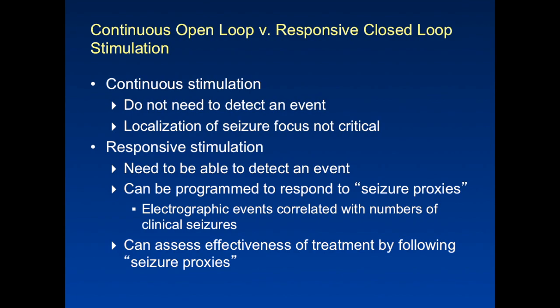So what are the advantages of continuous open loop versus responsive closed loop? Well, with continuous stimulation, you don't need to detect an event, so the patient doesn't have to be localized. And sometimes you can't localize a patient, and in that case, our system does not work. If you don't know where the seizure is coming from, you can't apply our technology. So with ours, you need to know where to put the leads, and you need to identify that you actually are in the right place, that you're detecting pathologic events.